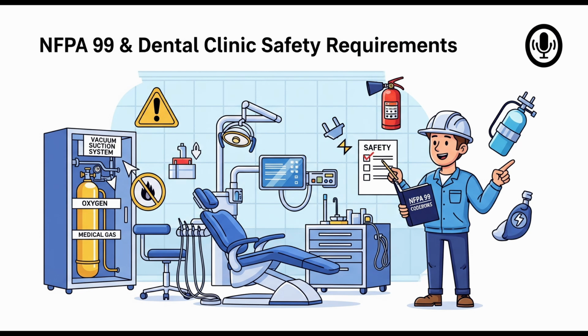But the really big change, also from 2012, was the shift to a risk-based approach. Okay, risk-based, that sounds key. What does that mean, practically speaking? It means the level of safety features required for things like medical gas systems, electrical power, isn't just based on whether it's a hospital or a clinic anymore. It's based on the potential risk to the patient if that system fails during a procedure. So the procedure's risk dictates the system requirements, not the building type. Precisely. So a procedure with a certain level of risk needs the same level of system safety support, whether it's happening in a huge medical center or a small outpatient office. It's a fundamental shift. Got it. So that's the lens we need.